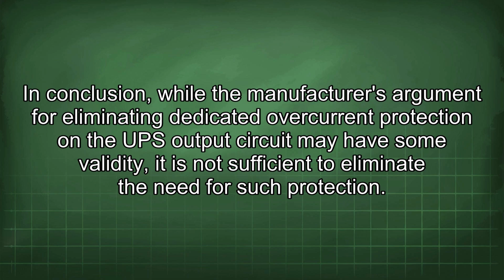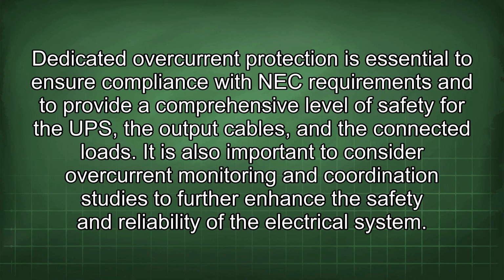In conclusion, while the manufacturer's argument for eliminating dedicated overcurrent protection on the UPS output circuit may have some validity, it is not sufficient to eliminate the need for such protection. Dedicated overcurrent protection is essential to ensure compliance with NEC requirements and to provide a comprehensive level of safety for the UPS, the output cables, and the connected loads. It is also important to consider overcurrent monitoring and coordination studies to further enhance the safety and reliability of the electrical system.